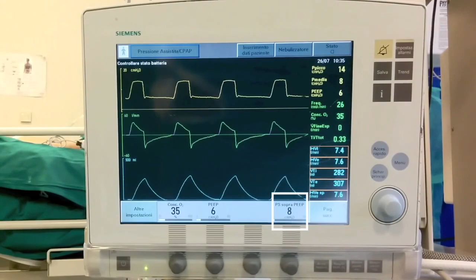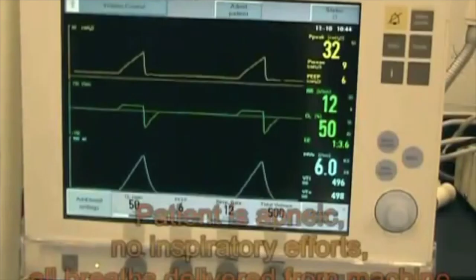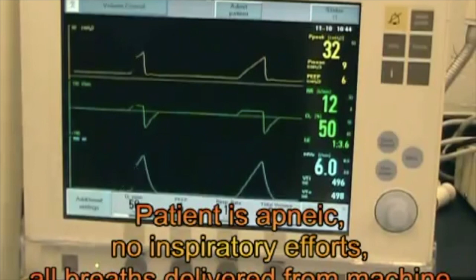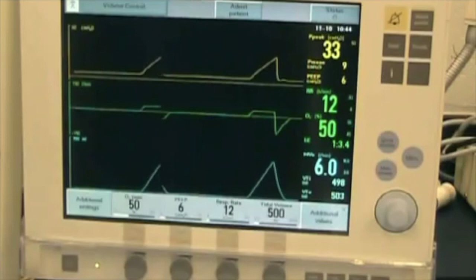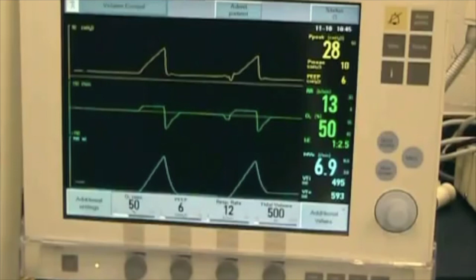Pressure control mode is a pressure-targeted, time-cycled mode of ventilation. During inspiration, the ventilator adjusts the flow rate to keep the airway pressure at the set level. Therefore, the ventilator delivers the preset pressure regardless of the patient's own inspiratory efforts. The other one is assist control mode, which is a volume-cycled mode of ventilation. It works by setting a fixed tidal volume that the ventilator will deliver at set intervals of time or when the patient initiates a breath. The machine will respond to every patient breath. If the patient stops breathing, the machine keeps delivering breaths, and if the patient starts breathing and is anxious and takes a lot of breaths in a row, the rate will increase.